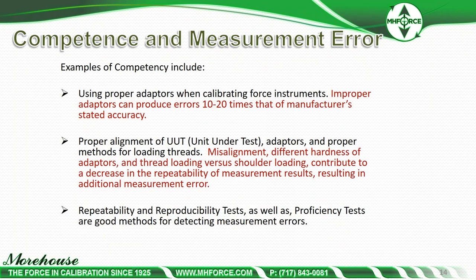Some examples of competence and measurement error. Improper adapters can produce errors 10 to 20 times that of the manufacturer's stated accuracy. Proper alignment of the unit under test, adapters, and proper methods for loading threads — misalignment and different hardness of adapters — all contribute to a decrease in repeatability and additional measurement error. Repeatability and reproducibility tests as well as proficiency tests are good methods for detecting measurement errors.